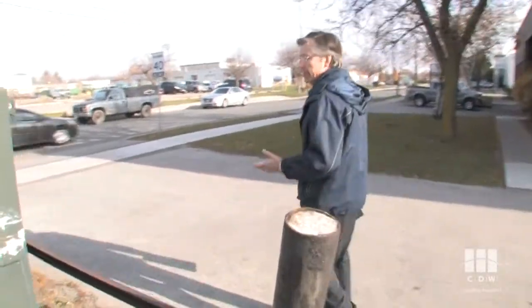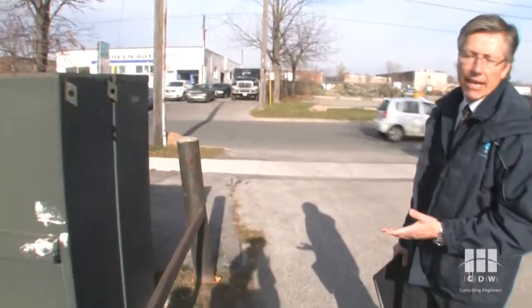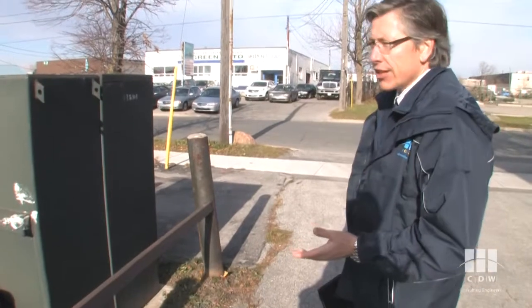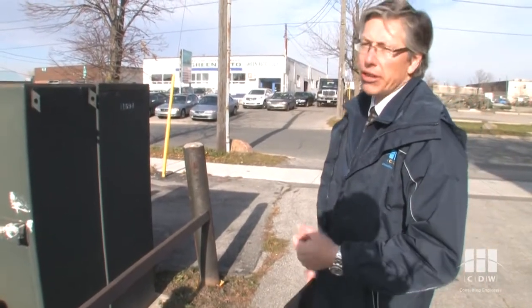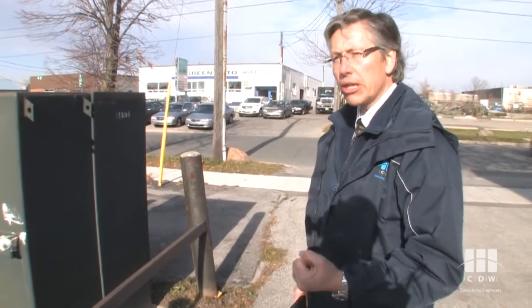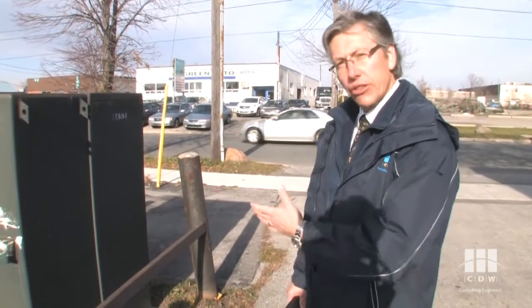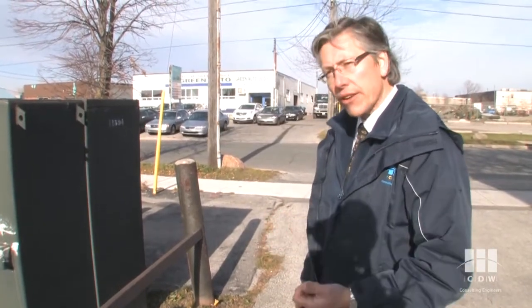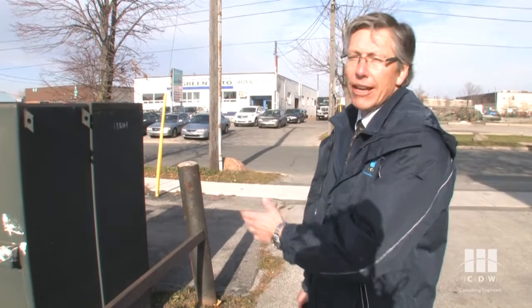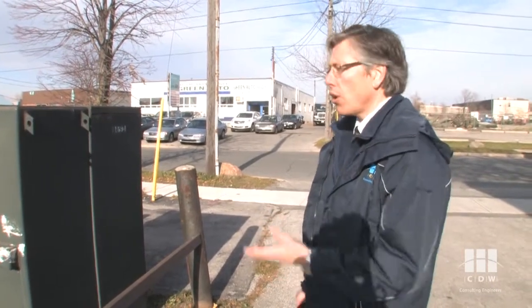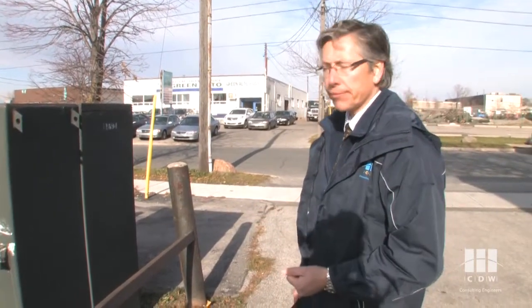In this particular case, I don't have a size, so I don't know how many kVA this transformer is. If I really wanted to know, or the client needed to know the power to the building, you'd have to call the utility provider, give them the address or the transformer number, and they can usually tell you over the phone how many kVA the transformer is.